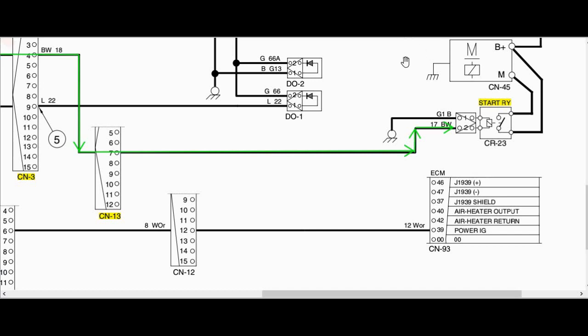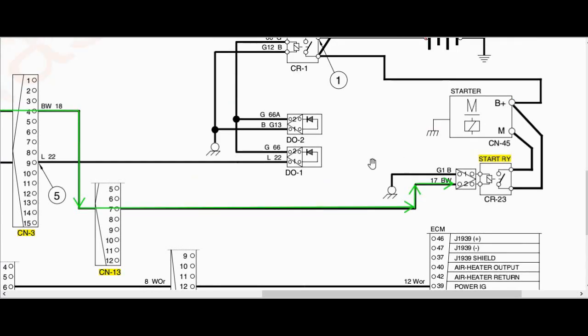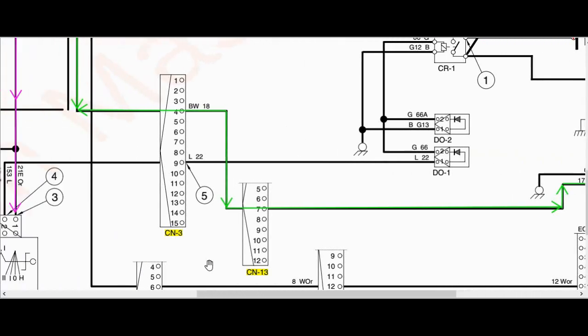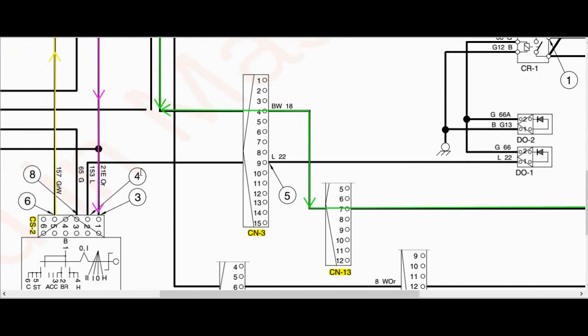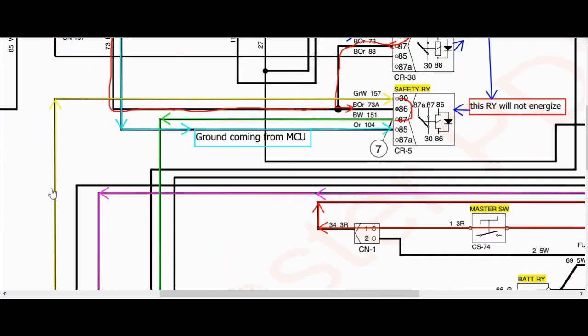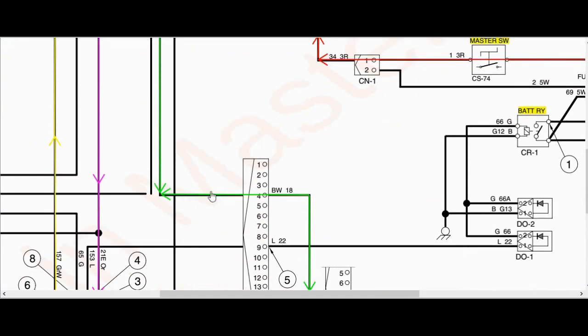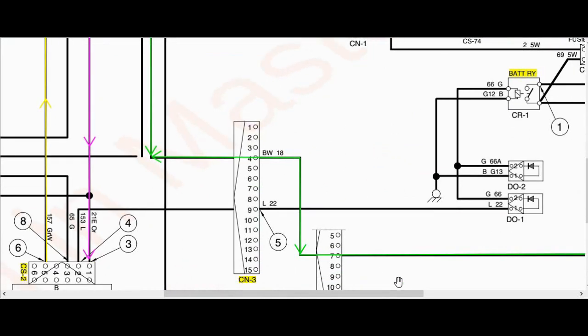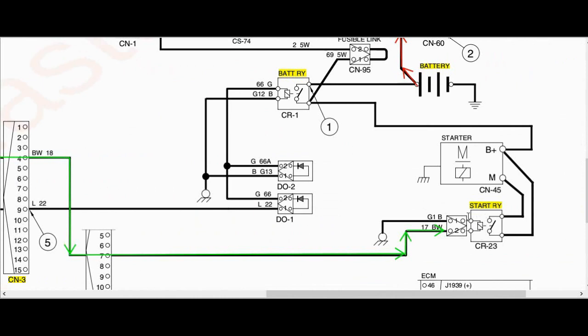So now what we need to note is to keep the machine in the on position and check the continuity between pin number 5 of the start switch and the start relay. If this condition is true and this path shows continuity but the machine does not start, then there will be another fault. Now let's move to the machine and start the diagnostic process physically.